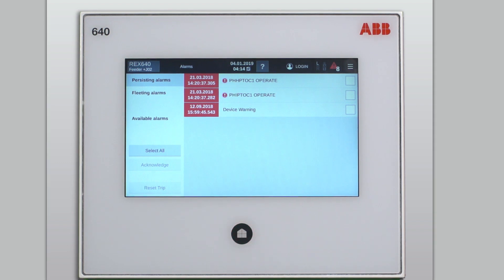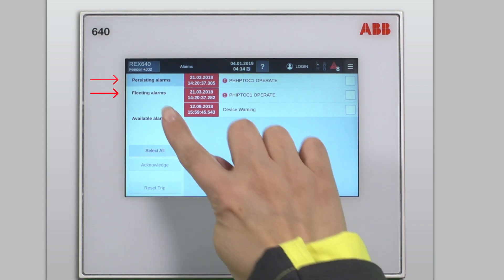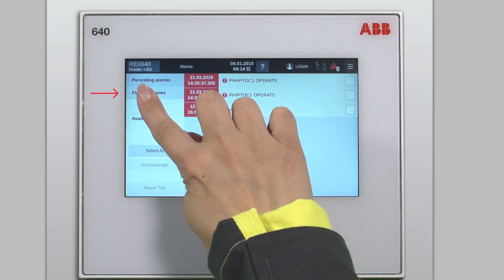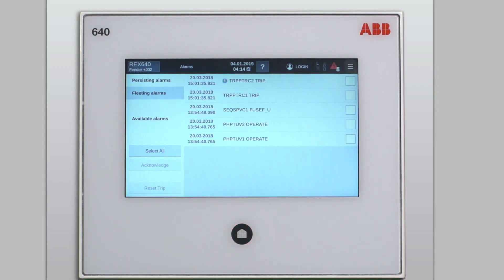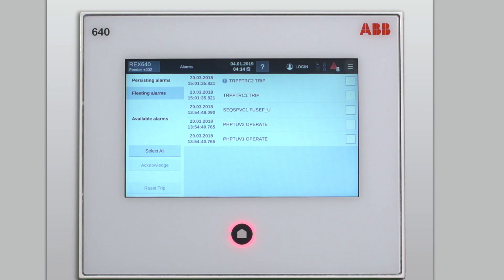On the alarm page, there are two categories of alarms: the persisting alarms and the fleeting alarms. Let's start with the fleeting alarms and acknowledge those. Fleeting alarms mean that they have been active sometime in the past, but they are not active anymore.